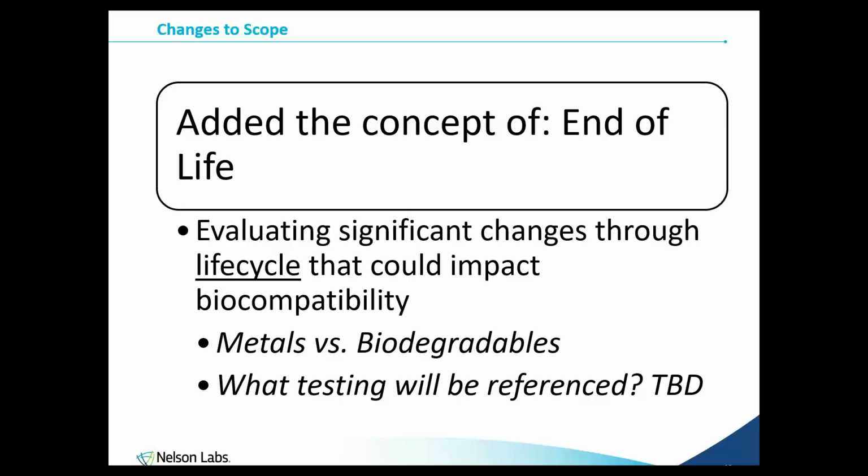even leachable profiles. And so the concept now is you have to evaluate your biocompatibility not just at time 0, but at the end of shelf life, and potentially in between, depending on your materials. We're not saying you have to redo all your biocompatibility. You have to just do some kind of evaluation at different endpoints in your life cycle to make sure that this device is not going to change its biocompatibility impact to the patient. So we're still kind of determining how this is going to be enforced, but this is something we're seeing today.